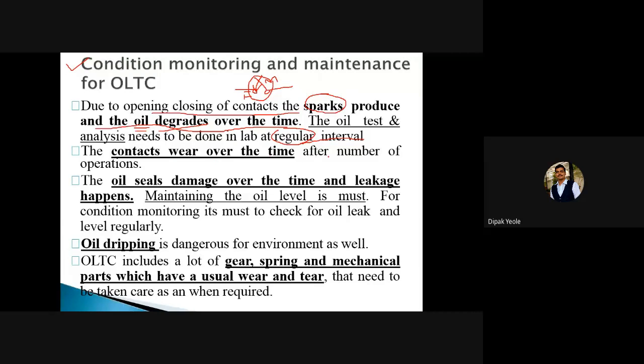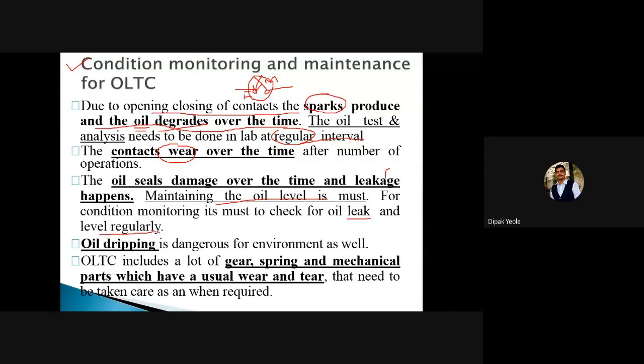The contacts wear over time after a number of operations, so wear and tear of contacts is possible. We have to take care of those contacts. The oil seals damage over time and leakage happens. The oil we require for the arc extinguishing purpose is going to damage over time, and there might be a condition where leakage happens. Maintaining the oil level is a must, because if leakage is available we have to remove it to maintain the oil level constant. It is a must to check for oil leaks and level regularly.